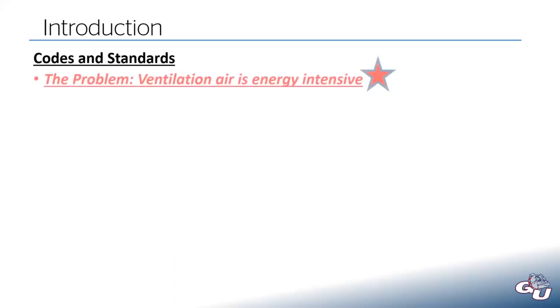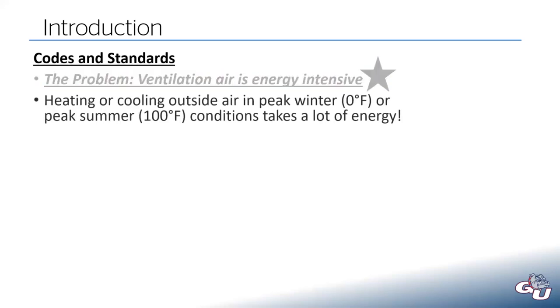The problem with ventilation air is it is very energy intensive to deal with. If you think about heating or cooling that outside air that we're bringing into the building, if we're in a peak winter day and it's 0 degrees outside, it takes a lot of energy to heat that air up. Or if we're in peak summer conditions and it's 100 degrees outside, it takes a lot of energy to cool that down. It's very energy intensive.